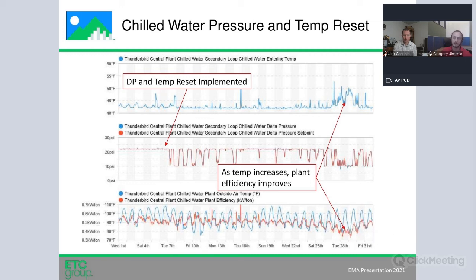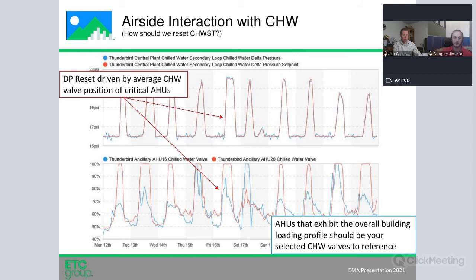And just to reiterate, a lower kW per ton is better. It's basically less energy consumed to provide the same amount of ton of cooling. So this just gives you that example of really where the rubber hits the road, and saving the energy on the chiller really shows up from increasing that chilled water temperature. Yes, you do get pumping energy savings from the DP, but the largest consumer obviously has a larger impact on the chiller side of things.